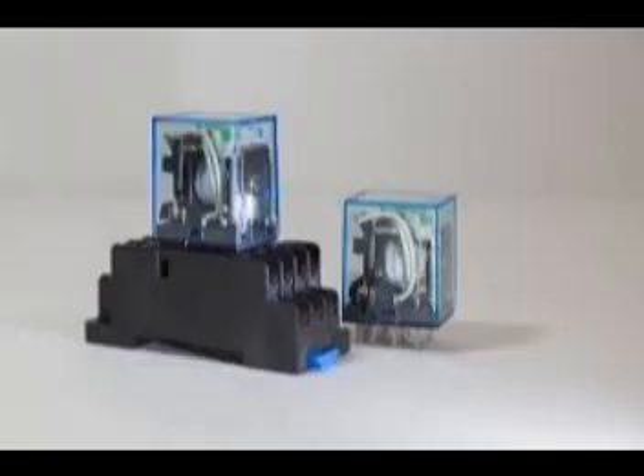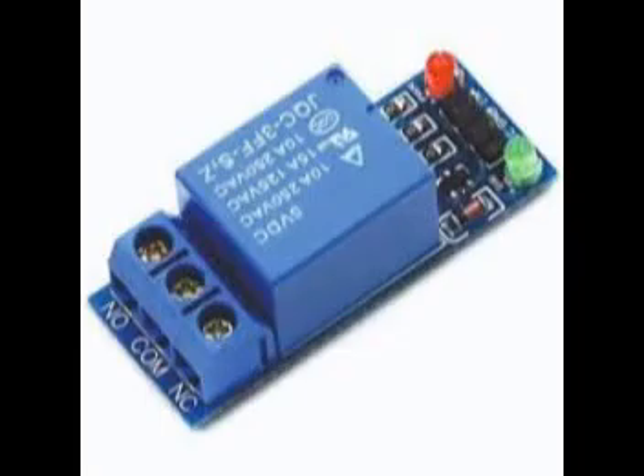They're more versatile. What's kind of cool here is that they essentially combine both a normally open and a normally closed contact, but they share a single common terminal. Interesting. So when the relay switches, one circuit is broken at the same time as the other one is made. It transfers the connection. And the document specifically mentions Form C contacts use a break before make action. Break before make.